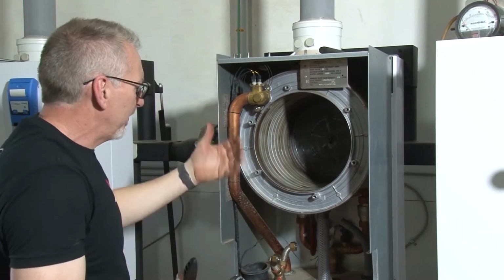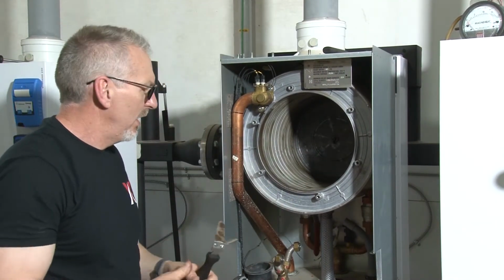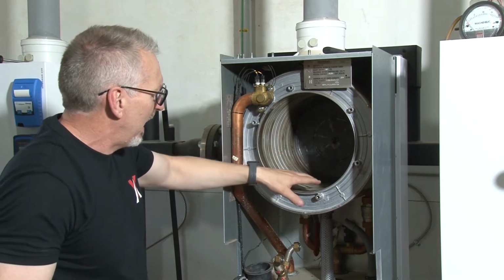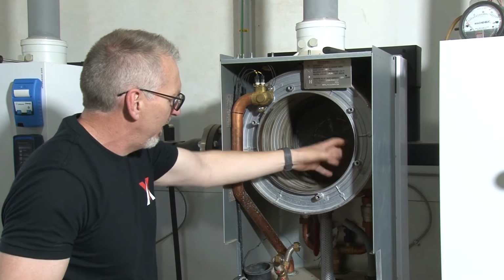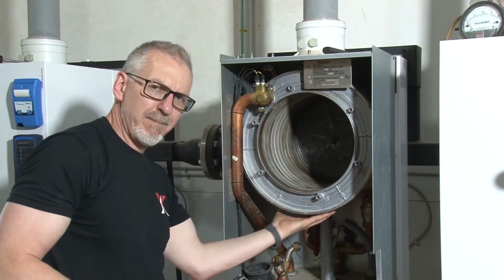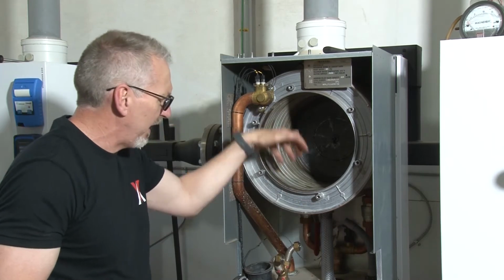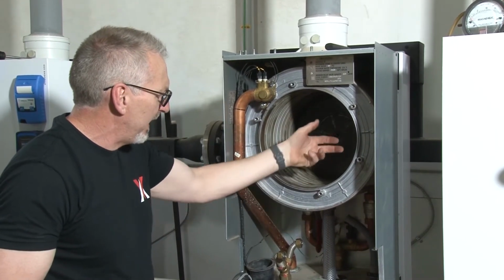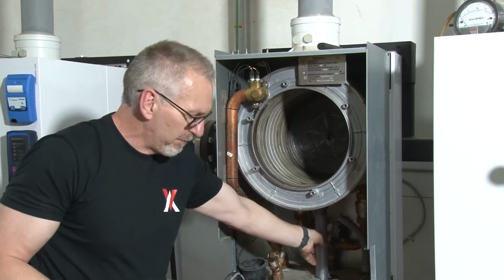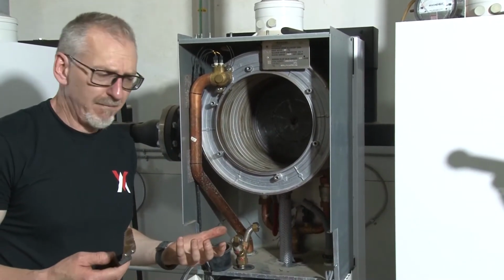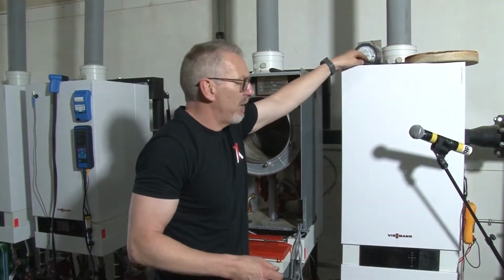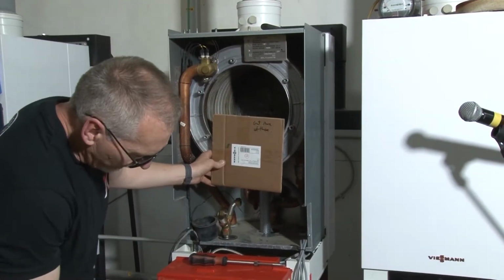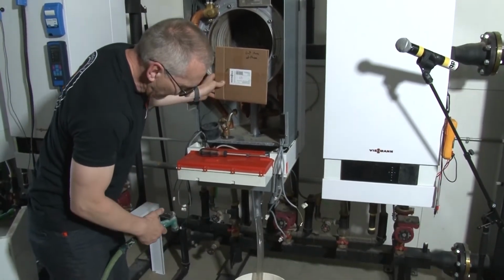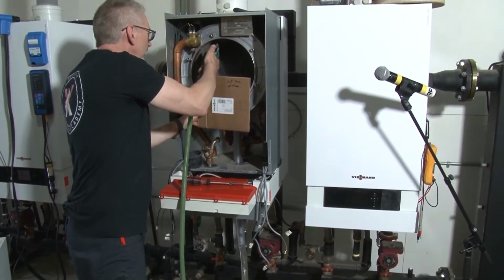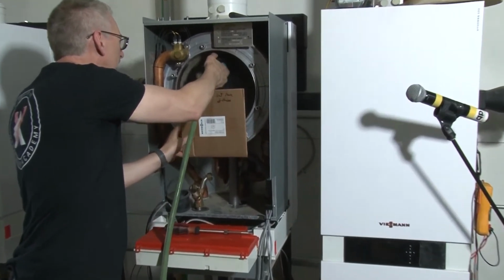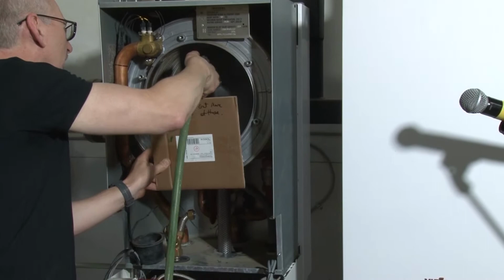And from there, once I get this clean, I would now take some water. And again, just flush this heat exchanger out. I'm getting rid of the chemical that I poured in there, A. And B is all of the debris that I got packed on the bottom here as a result of punching those flue gas passageways. I'm now going to get that stuff basically moved into this pipe and basically drain it out of the boiler, so it's not going to be part of a problem moving forward. So I'm going to grab the hose. The focus really is down on the drain here. What we're seeing coming out of the boiler on that side. Getting all that chemical basically washed out.